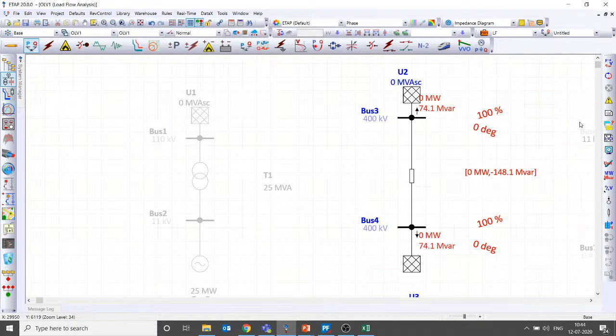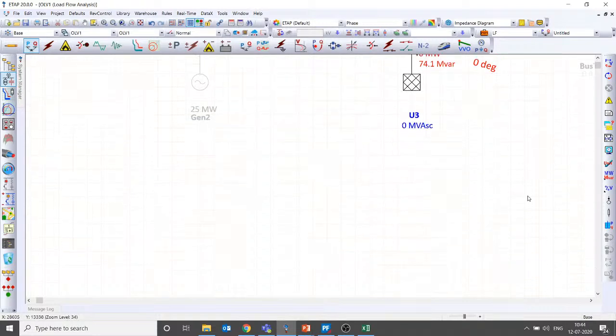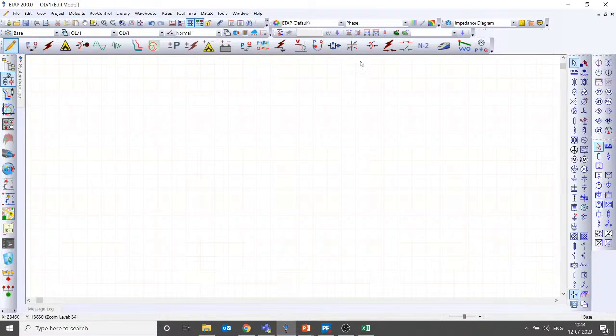Then you need to ask a question, why do you need to model this multiple slack bus or multiple grids? It is not advisable to connect two different sources within your industry. For example, if you have an industry which receives the power supply at say 110 kV from ABC place, and if you are getting some other 110 kV from XYZ, it is not allowed or not advisable to parallel these two sources. One is from the location called ABC and the other one is called XYZ. That's not really advisable. Let me simulate and tell why.